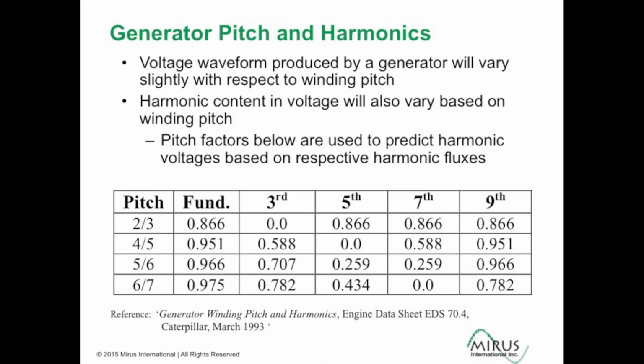So the question often asked is, if a 2/3 pitch generator produces less third harmonic voltage distortion, will it be a better option for reducing circulating current that is typically triple frequency? Many would say yes, but I would argue no, and we'll explain that in a few slides going forward.